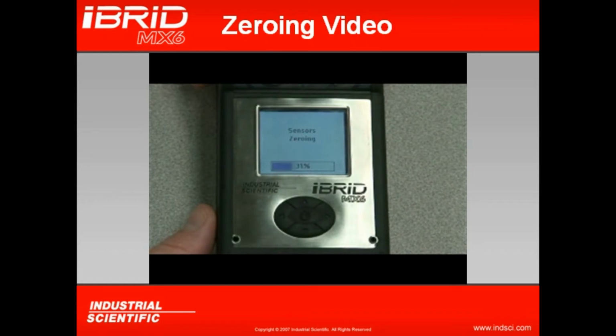It's going to take your toxics and your combustibles and set them to 0 automatically. Upon completing this, it'll then automatically start the calibration of the oxygen sensor. So at this point, the oxygen sensor is calibrating itself to the room air. As we said previously, we always want to ensure we do this only in fresh air, because the O2 full span and that O2 calibration is based on the oxygen concentration in the ambient atmosphere.